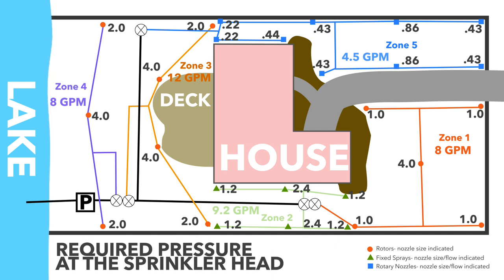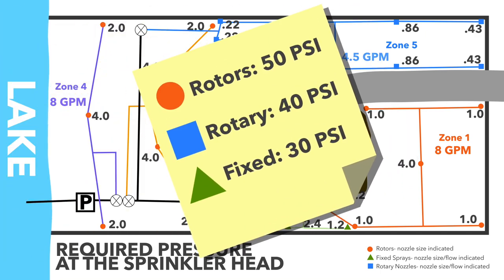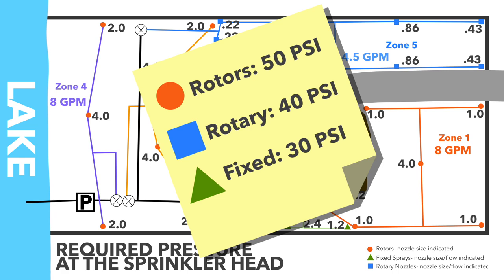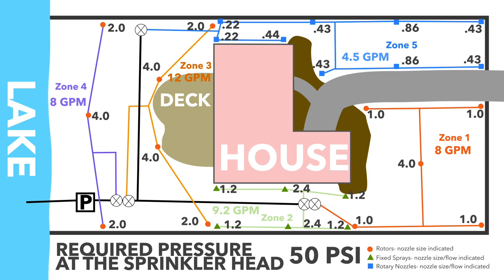The required pressure at the sprinkler head is based on sprinkler type. The rotors in zones 1, 3, and 4 require 50 PSI; the rotary nozzles in zone 5 require 40 PSI; and the fixed sprays in zone 2 require 30 PSI. To ensure the system can handle all three types, we select 50 PSI as the required pressure for the system.